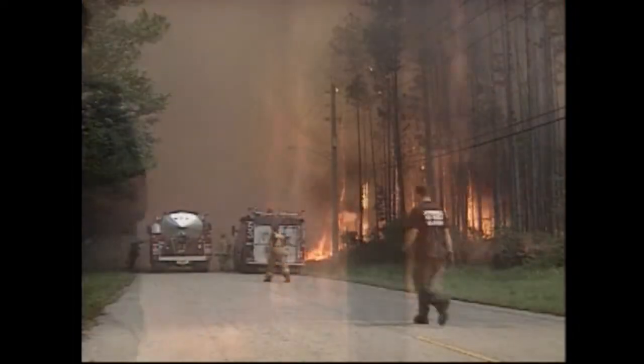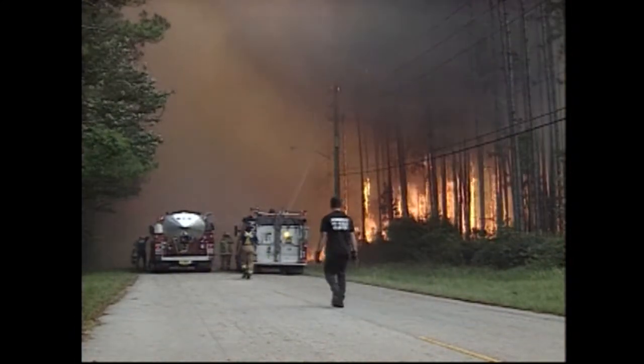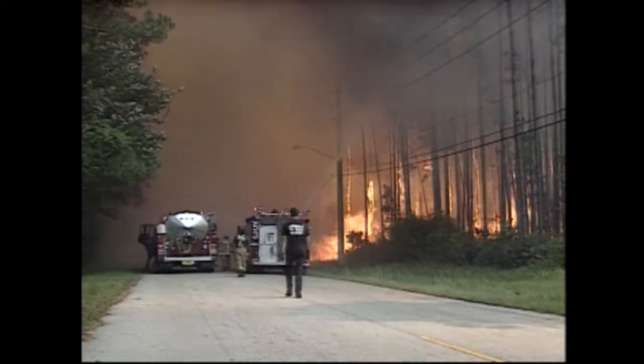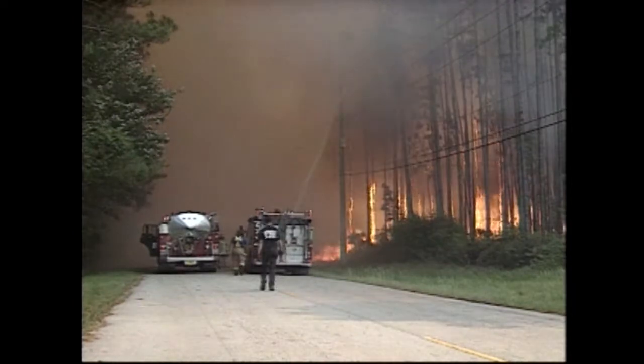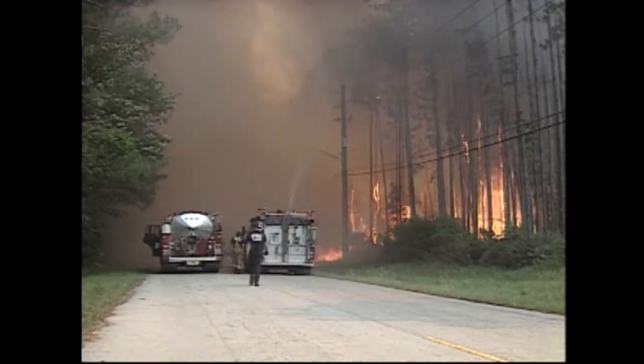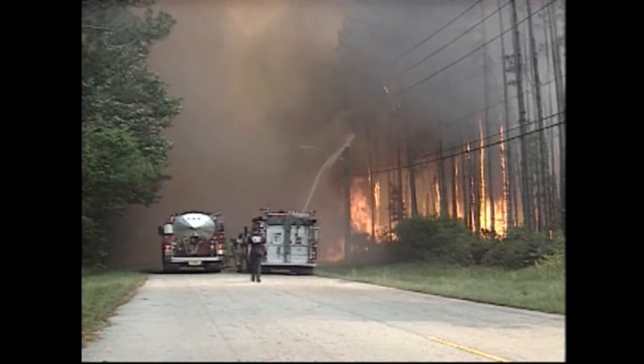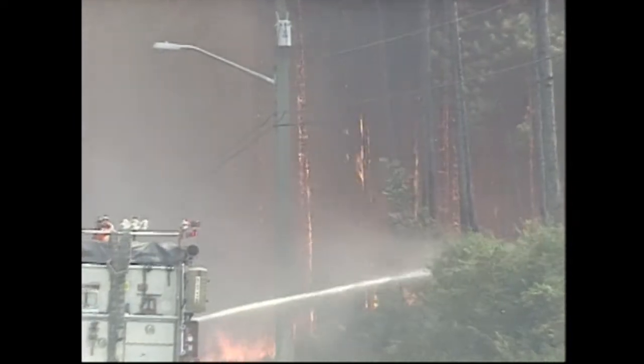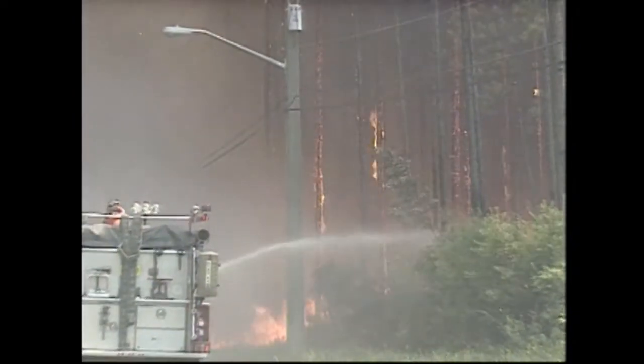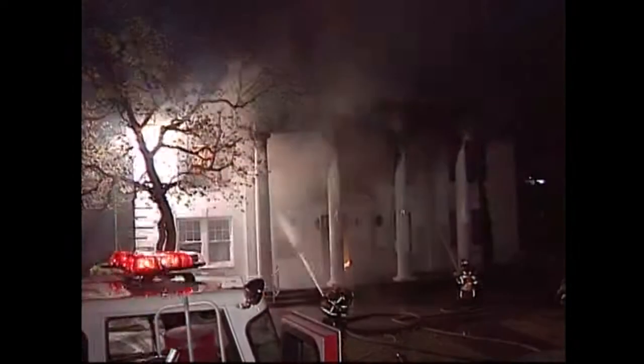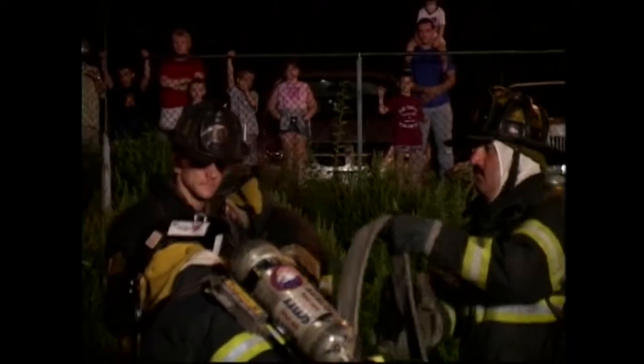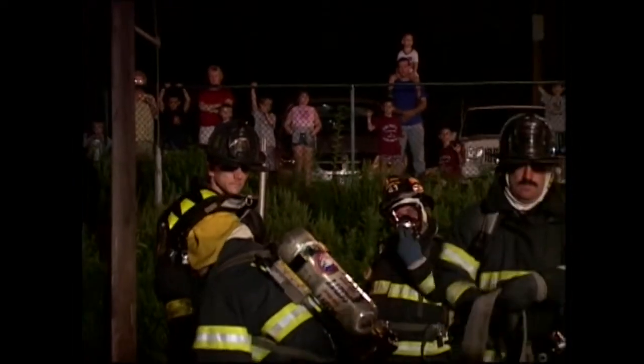The utility company people will advise you on what to do when they arrive. They may very well direct you to let it burn, or wait until power is shut off before trying to suppress the fire. This doesn't mean there aren't actions which can be taken to provide a safer outcome. There are usually numerous exposures, such as trees and buildings, which need to be protected from fire. Also, securing the site includes keeping the public at a safe distance until the emergency is resolved.